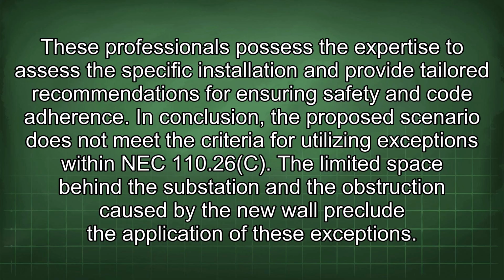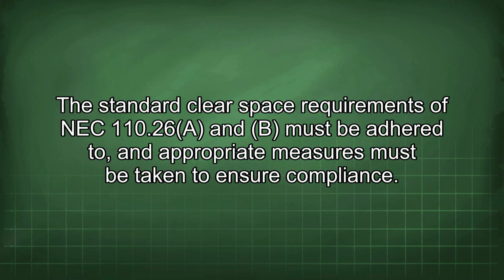In conclusion, the proposed scenario does not meet the criteria for utilizing exceptions within NEC 110.26(C). The limited space behind the substation and the obstruction caused by the new wall preclude the application of these exceptions. The standard clear space requirements of NEC 110.26(A) and (B) must be adhered to, and appropriate measures must be taken to ensure compliance.